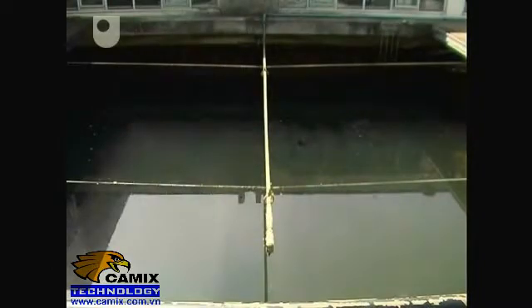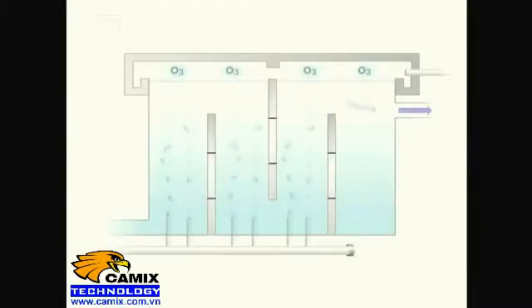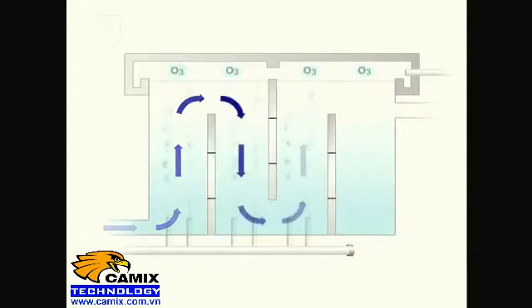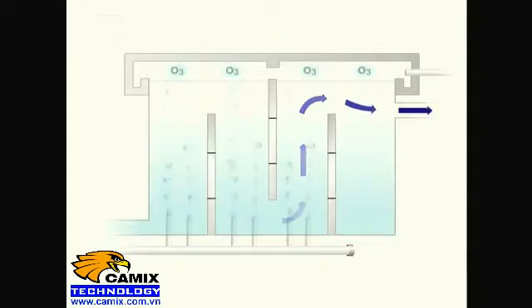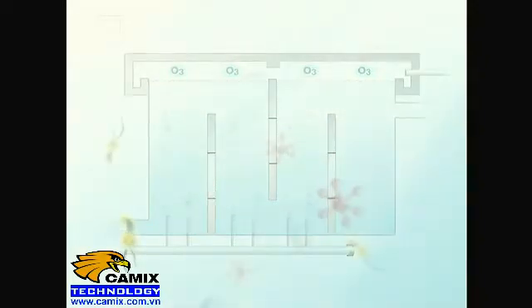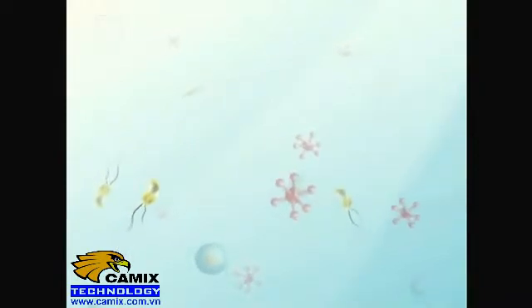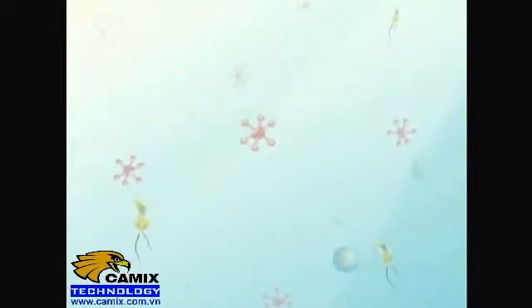This is the last point in the process where the water is exposed to light. The clean water from the rapid gravity filters is then pumped into secondary ozonation tanks, primarily to break down any pesticides that may be present in the water. But also, the ozone oxidises any trace organic compounds, and kills any viruses and bacteria.